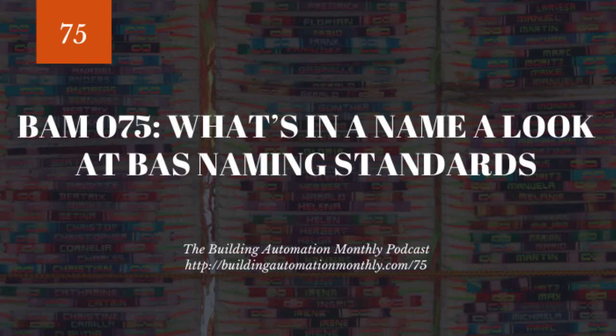On top of that, you struggle now because if you want to train someone on a common graphic, a common naming scheme, a common point scheme, you can't do that. And the third final issue is on the analytics and fault detection side. If everything's called temperature and you need to plug certain points into a fault system so that you can see simultaneous heating and cooling, or just bad control, or PID loops that are getting out of tune, well, if everything's called temp and everything's called set point, then what is the temp? Which one's the right temp? Which one's the right set point? And so you can start to see how this can become a really big nightmare.